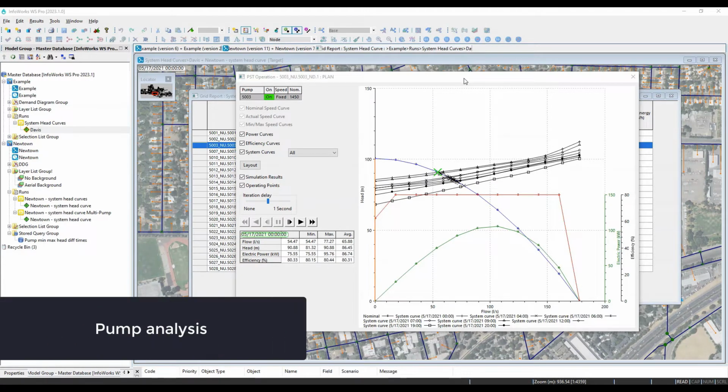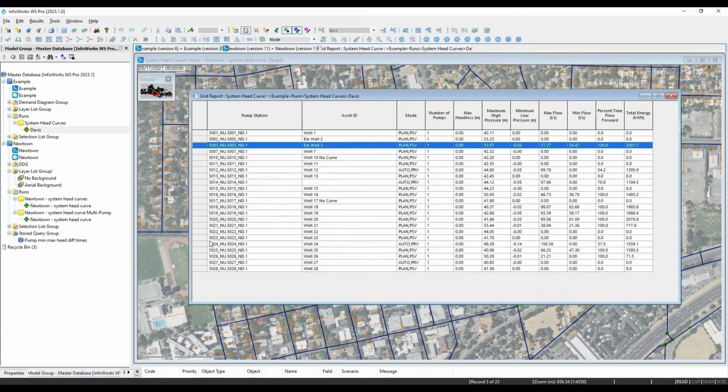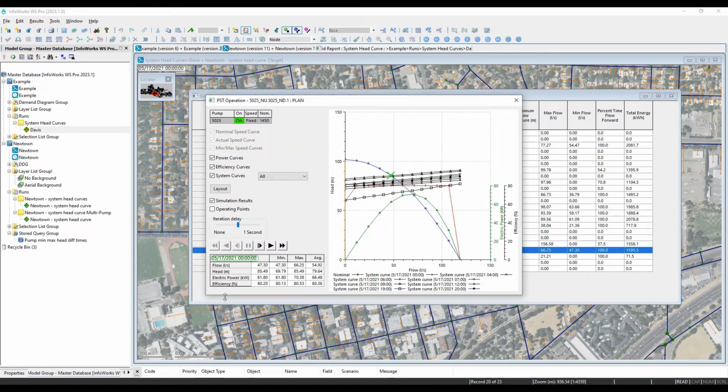So what can we do with these results? Since we now know the hypothetical head requirements for any flow at this location, we can consider alternative pumps. Starting with the existing pump, we see that the intersections are too high in the curve, which can lead to inefficiency and additional wear. The slope of the curve can also inform future changes. A steep curve implies high system losses, so if you need more flow, you'll also need a pump that can deliver a bit more head. Likewise, a pump with really flat curves means that there is very little head loss, and so you can supply a lot more flow without the head penalty.